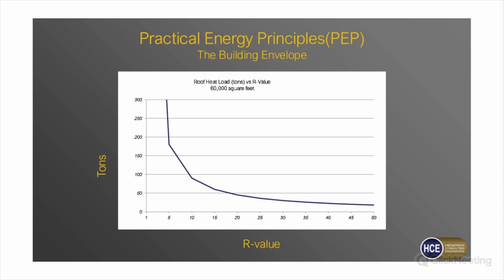We do the same comparison for the roof, and it's a similar curve, just with different numbers. This is for a fixed amount of roof square footage, so it would ratio out similarly for a bigger or smaller school. On the lower end, an R value of 5 puts us up close to 300 tons. As we move down the graph with a bigger R value, we can get well below 50, maybe close to 20 or 25. At around R30, it's pretty convenient to pay for that value and pick up all the energy savings you can. So whenever you're talking with your architect, building standards people, facilities people, or considering a cost savings measure, you want to know how this will affect your air conditioning.